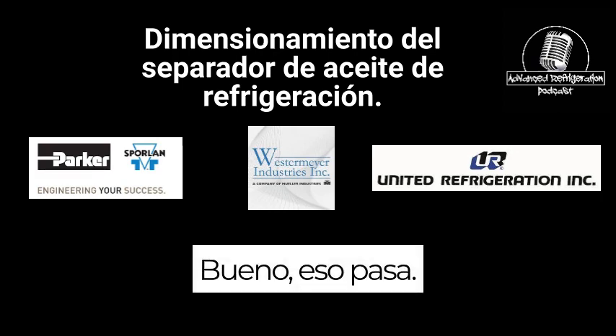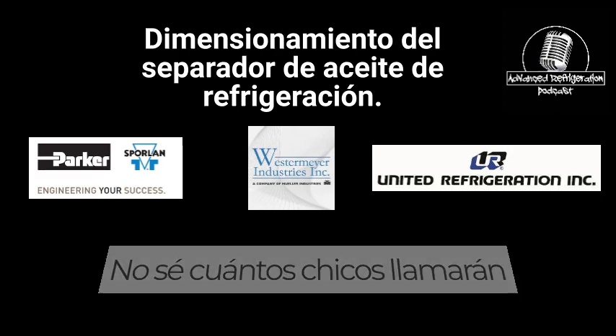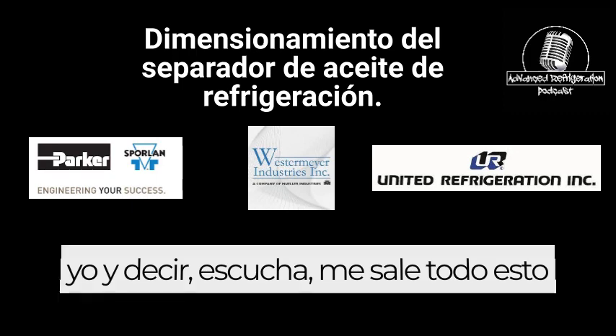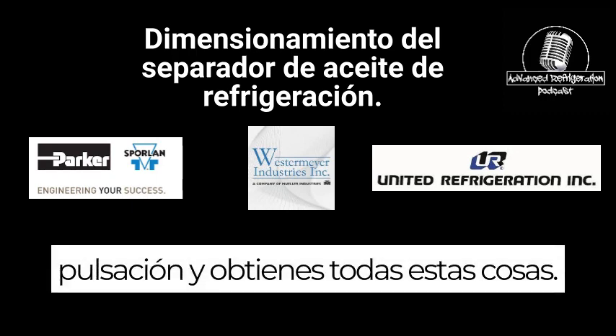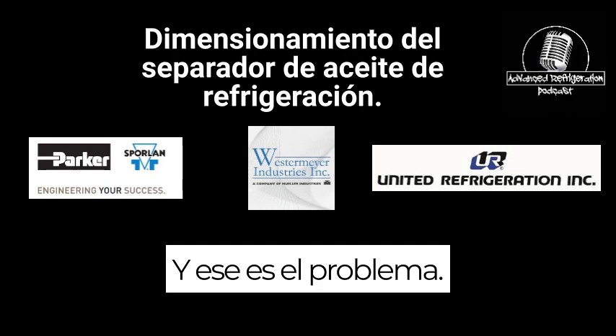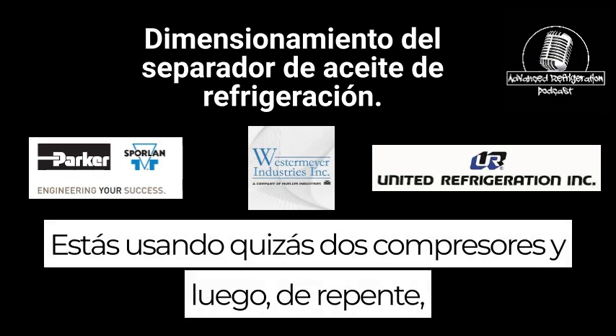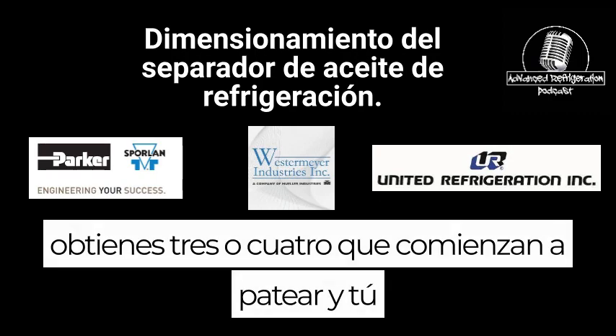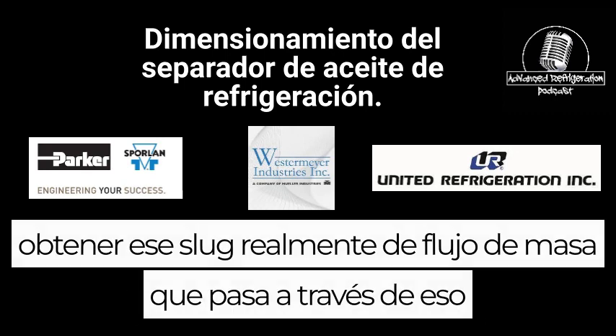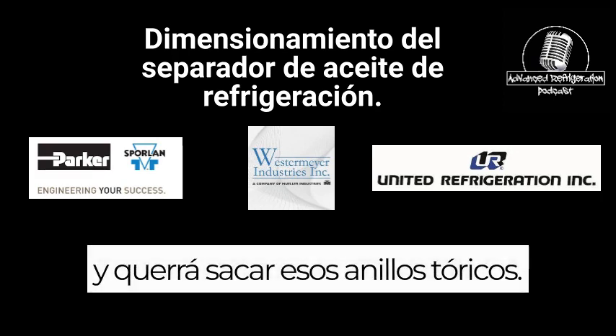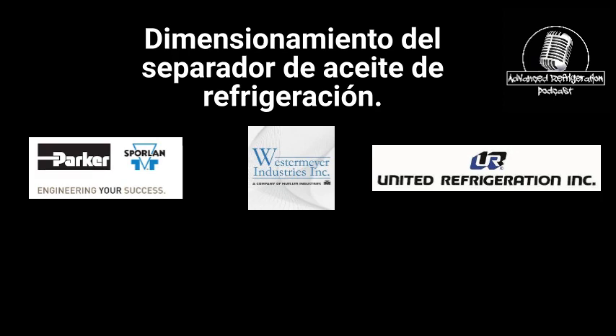Well, that does happen. I don't know how many guys will call me and say, listen, I get all this pulsation. And that's the problem, is that you're running maybe 2 compressors, and then all of a sudden 3 or 4 start kicking on, and you get that slug of mass flow that comes through, and it'll want to pop those O-rings out.